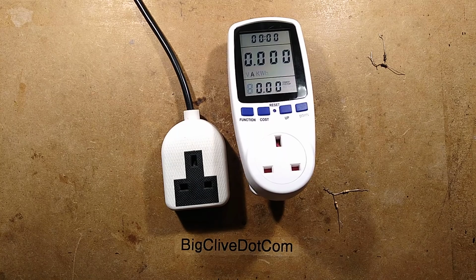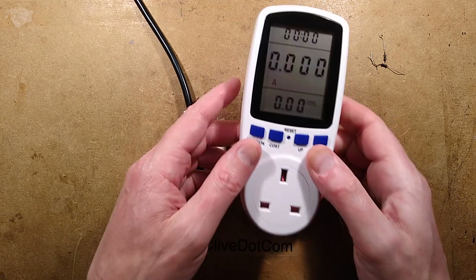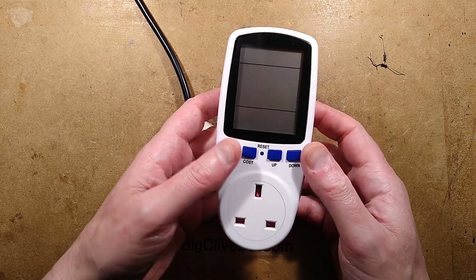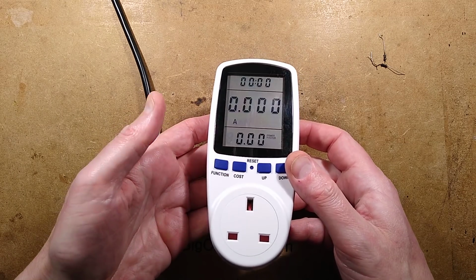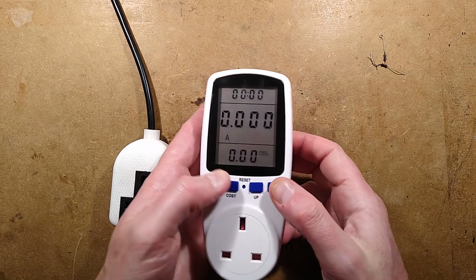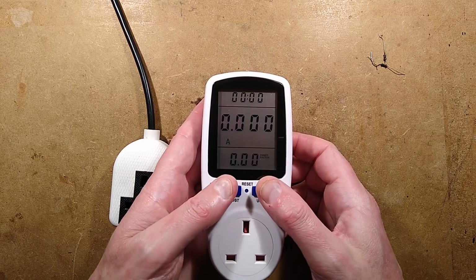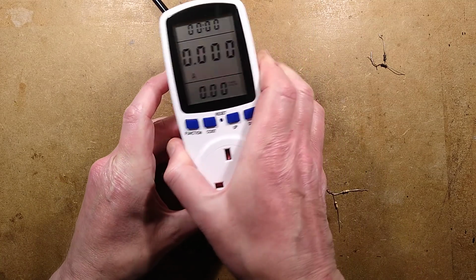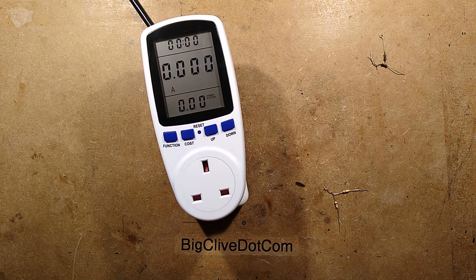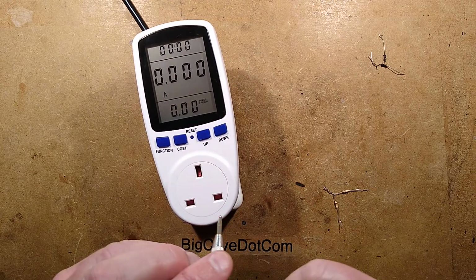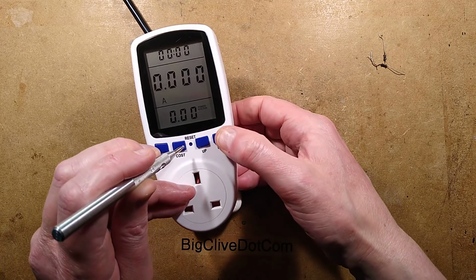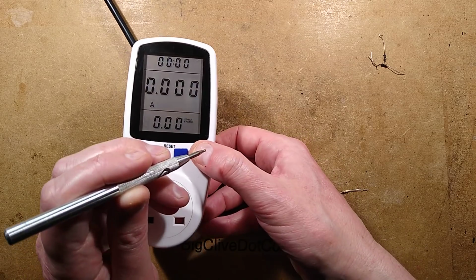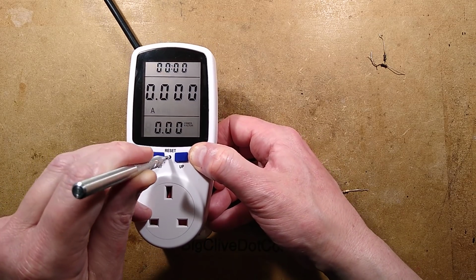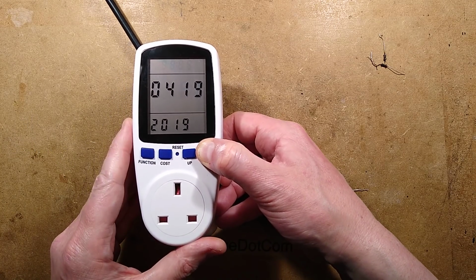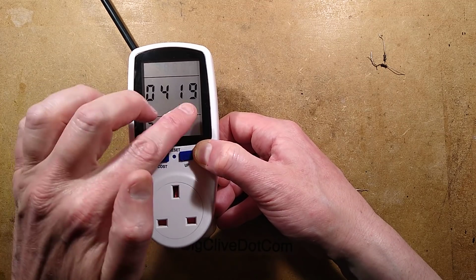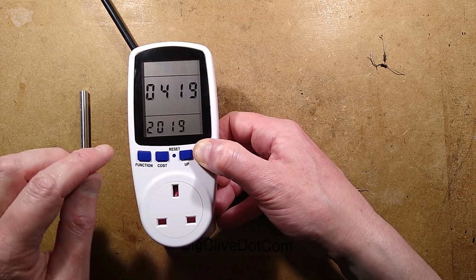Oh, there is one other thing I noticed. I was trying every button combination, and there is a battery in it, by the way. When you press this button, it wakes it up. I tried every button combination to see if I could put it into calibration mode, and I found one mode that might be calibration mode. I'm guessing it'll be software calibration. It's how they normally do it. If you press down, and I'll hold this at an angle, and you reset it, and then you hold the button and it goes 0419, could that be the month and year it was made?